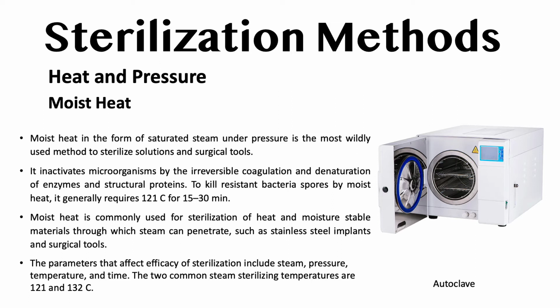The parameters that affect efficacy of sterilization include steam, pressure, temperature, and time. The two common steam sterilization temperature are 121 and 132 degrees centigrade.